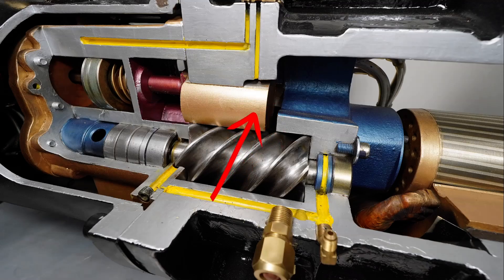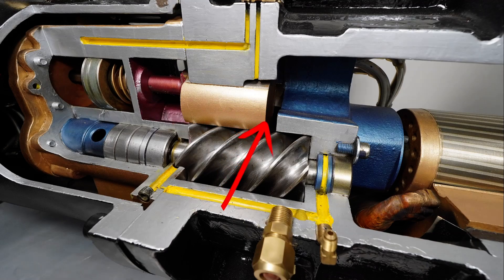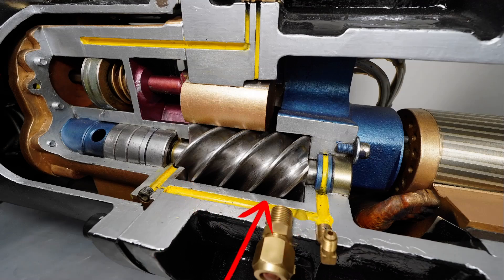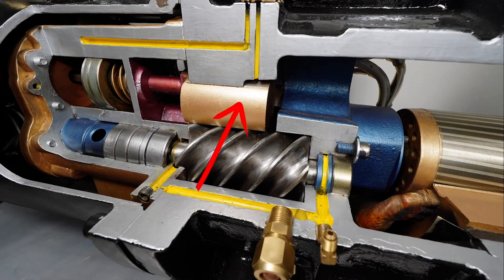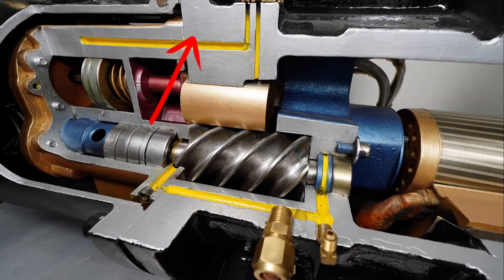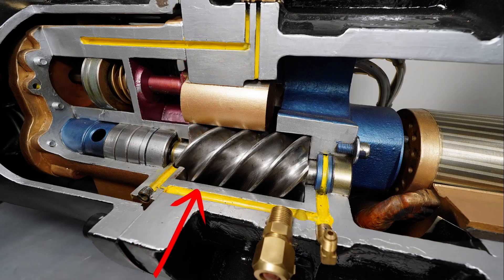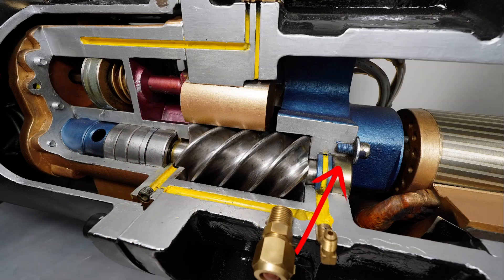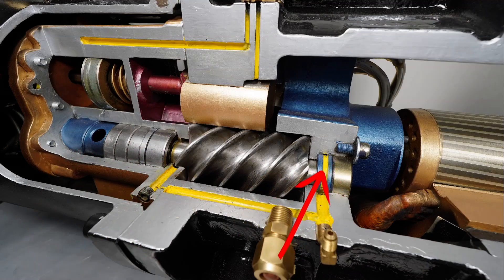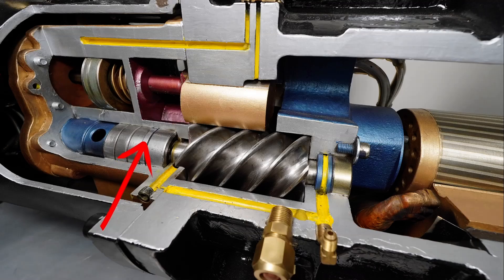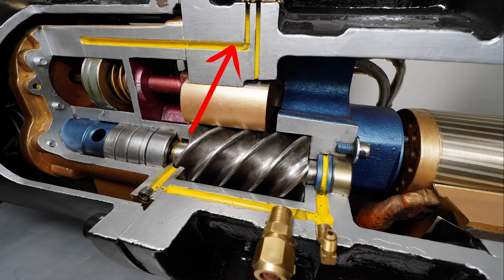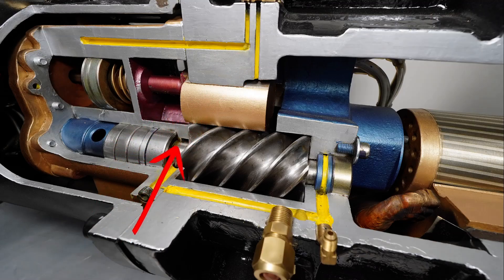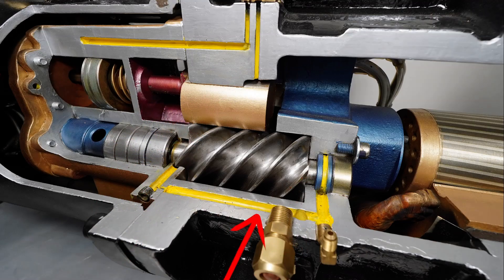So what you're seeing right here is this compressor is mostly loaded. The whole underbelly of this compressor is exposed. There is no sealing surface down there. It is just up here where this slide is. And you'll see these oil ports, all these yellow marks. These are oil ports. Now these ports down here are feeding our bearings. And this bearing, these bearing chambers or assemblies are in the low pressure side of the system. We use differential pressure, high pressure oil to feed into our low pressure side. So I just want you to understand what these are.